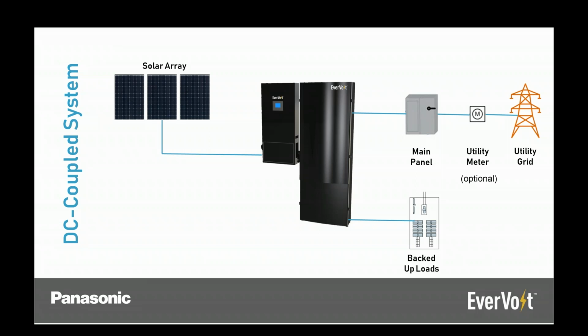So there's a couple different ways to install energy storage. First, we'll start with the DC coupled system. It has its advantages, which we'll get into, but it's a very simple concept where there's generally a single inverter. You have your PV array going directly into that inverter, and then you have a sub panel with your backed up loads - these are the loads that the homeowner chooses to have during an outage. Then you have your inverter tied into your main service panel, very similar to the traditional solar PV string inverter type systems, and then you have your battery cabinet.